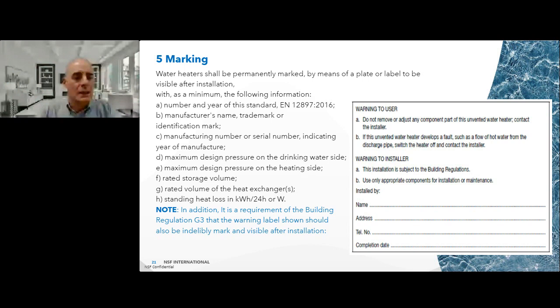The rated storage volume, the rated volume of the heat exchanger or heat exchangers, and the standing heat loss in kilowatt hours per 24 hours or watts. Note that in addition, it is a requirement of the Building Regulation G3 that the warning labels shown should also be indelibly marked and visible after installation.